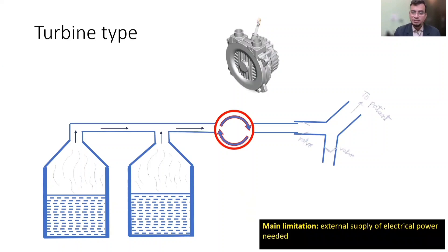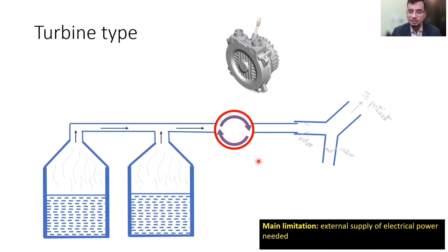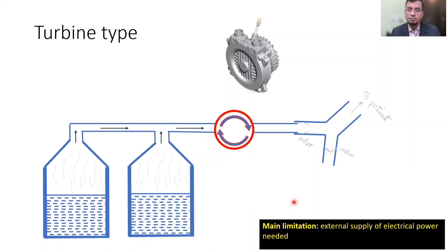The advanced solution is the turbine, added to compensate for enormous amounts of leak. Turbine-based ventilators generate very high flow rates sufficient for non-invasive ventilation. They require a low-pressure source of oxygen, which is an advantage. Turbines cut down cost and energy consumption, are very lightweight, can be easily handled and quickly transferred, and are very sturdy. They can be used in the ICU and are energy-efficient, durable for a very long time, and require minimal maintenance. The main limitation is that they always require an external supply of electrical power.